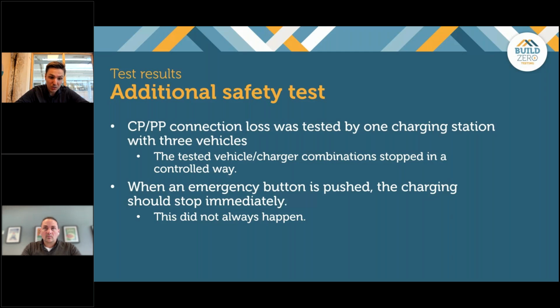We also tested what happens when the emergency button is used. Is the charging always stopped immediately, or does it happen gradually? We saw in some cases that it did not happen instantly, but gradually. In that case it's actually a stop button, not an emergency button, and it should not be used as one.